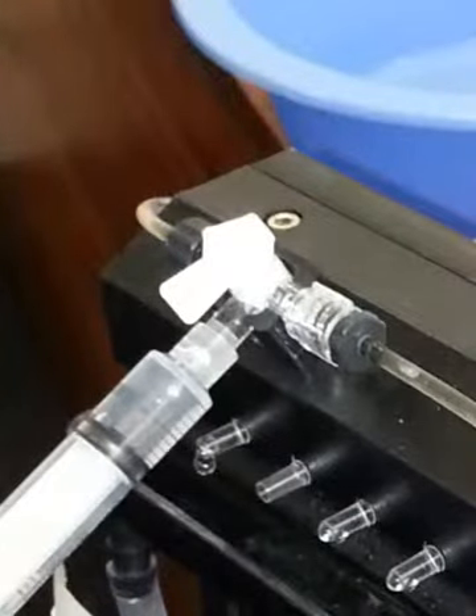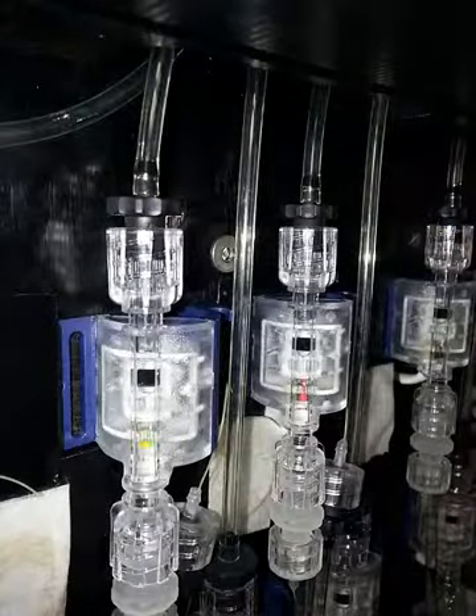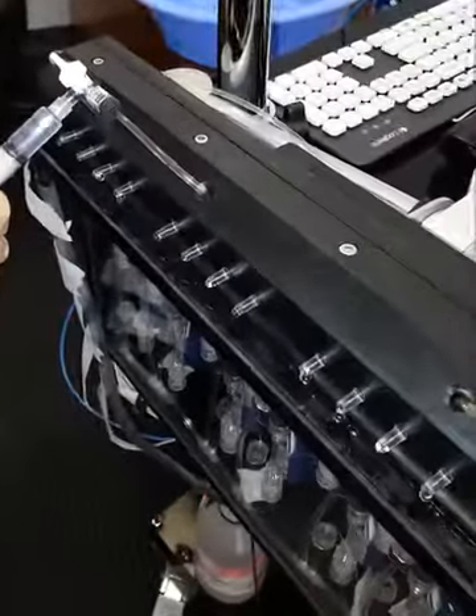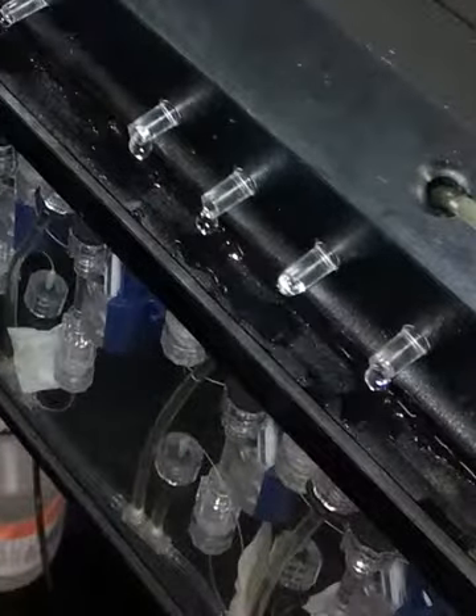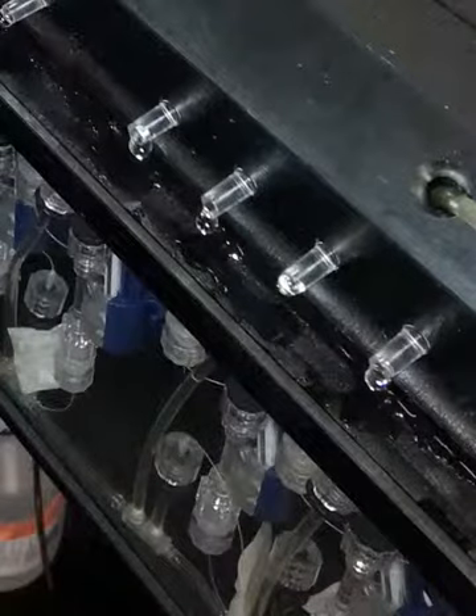After a couple of minutes, check the transducer chamber to see if it is now filled with water. If it is, in another few minutes you should see water dripping from the corresponding connector. If it does not fill with water, you should repeat the process, pressing harder or possibly using a smaller syringe, for example a 3 ml Luer lock syringe, which will generate a higher pressure. If this still does not work, the capillary may be blocked and would need to be changed. This should not occur if you have a water filter installed.